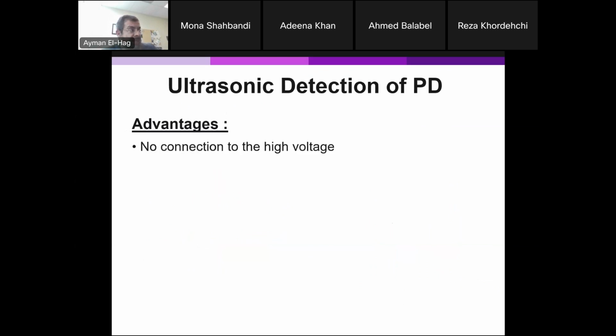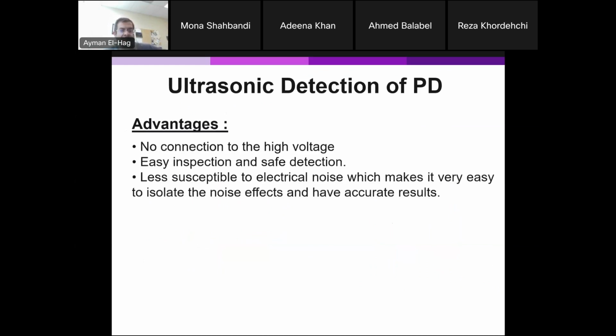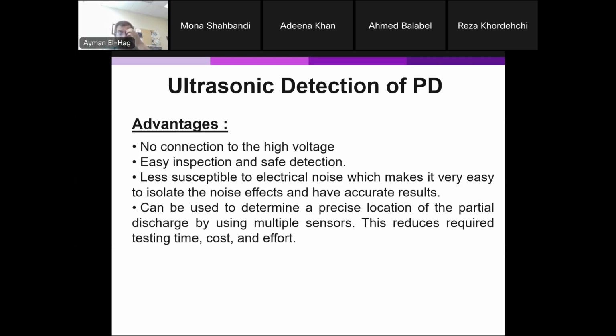So the advantages: there is no connection to high voltage. Again, this is an online detection of partial discharge. Easy inspection and safe detection as well. Because you are measuring sound, it is not interfered with by electromagnetic radiation. We mentioned that the RF antenna can detect any electromagnetic radiation, and nowadays you have a lot of it. This is immune from that. Now, someone might say we have a lot of mechanical noise around us. This is why you use the ultrasonic. In the ultrasonic range, it will measure only the sound that we cannot hear coming out of the source of the partial discharge.